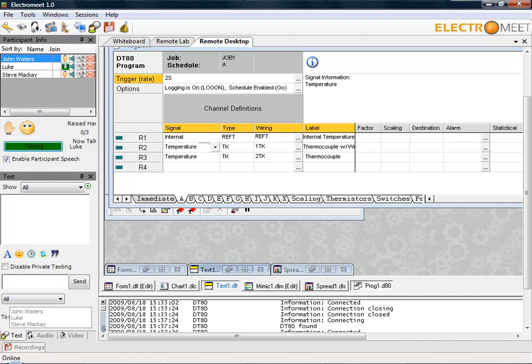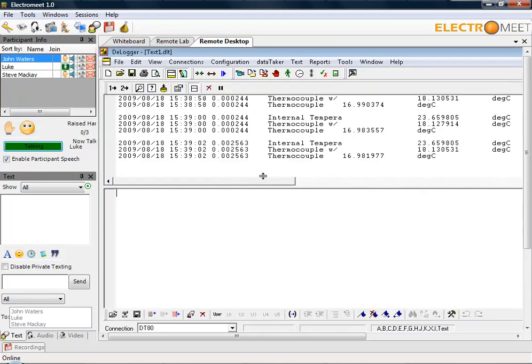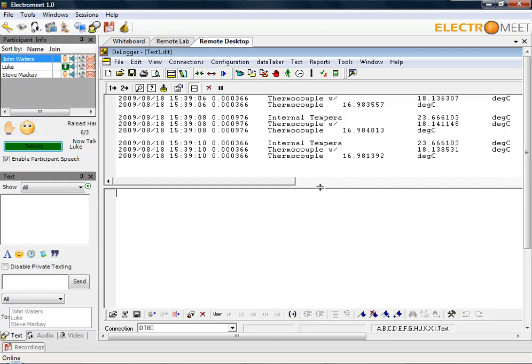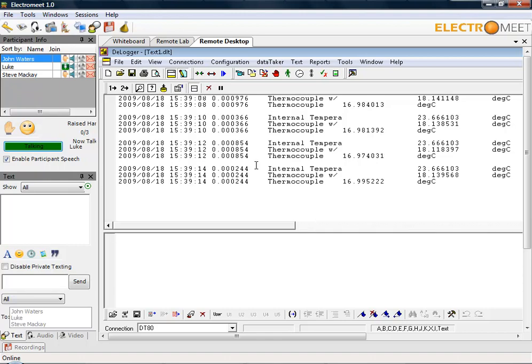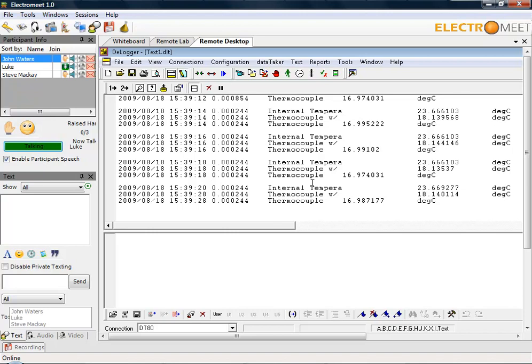Today we'll just quickly show you the text format. If I click on the text one dot dlt button as I've just done, it should bring up the text input screen. As you can see, I've specified the DT80 connection under the connection window and it will automatically start pulling in the data in a textual format from the data logger for each channel every two seconds.